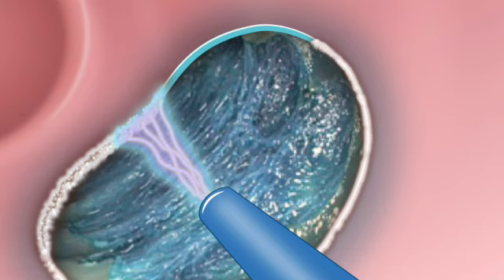The setup requires a specialized electrosurgical generator. And this generator isn't just a basic power source, it's simultaneously delivering two very distinct things down the catheter. The gas and the electricity. Precisely. A steady flow of argon gas and a high-voltage monopolar electrical current. Now, argon in its natural state is an inert, non-conductive, noble gas. It doesn't do anything on its own. It won't carry a charge.